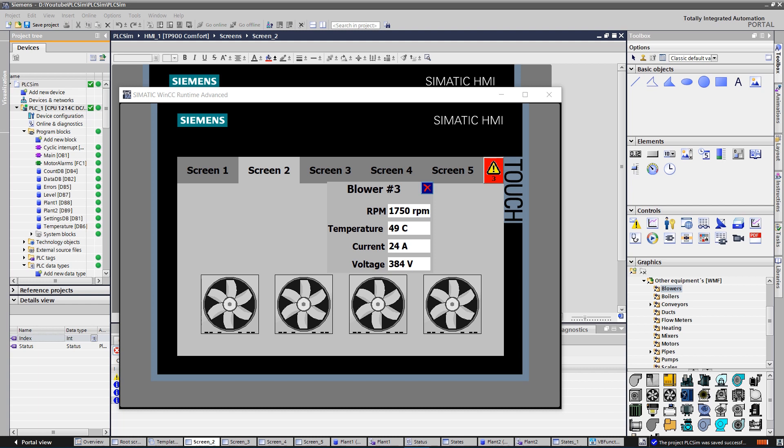Indirect addressing, or address multiplexing, is a very useful feature. By using it you need only one single tag to access a multitude of memory locations within the PLC's address range. You do not need to define a tag for each individual address if you want to read or write to it. So you need to define only one tag instead of 20, for example.